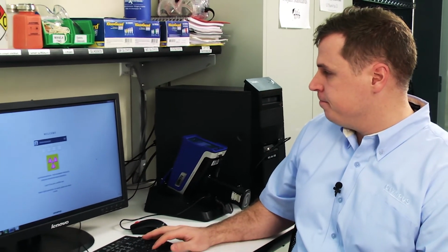Today I'm going to show you how to add your own custom notes template to the Vanta Analyzer. Adding your own notes template will allow you to make sure that any information relevant to your process is saved along with your data. To get started, just make sure that your Vanta Analyzer is connected to the PC and open the Vanta PC software.